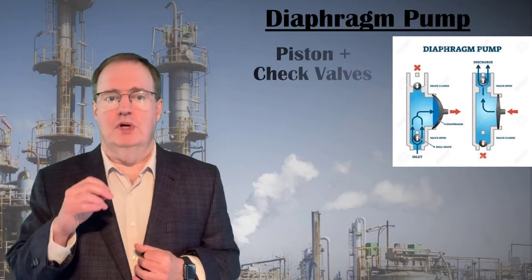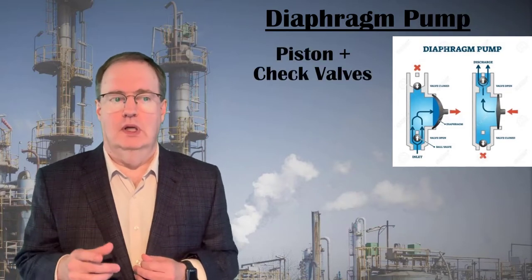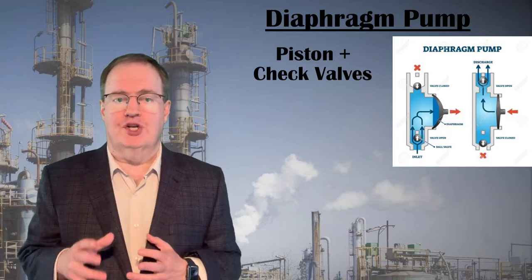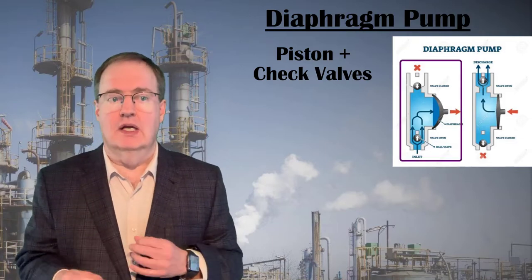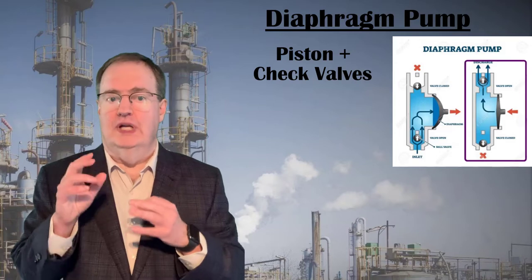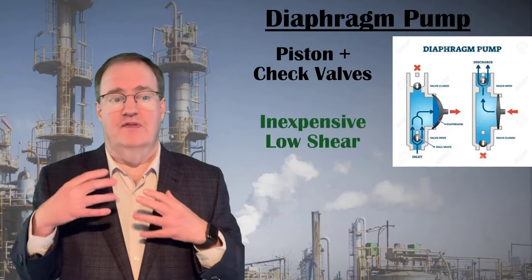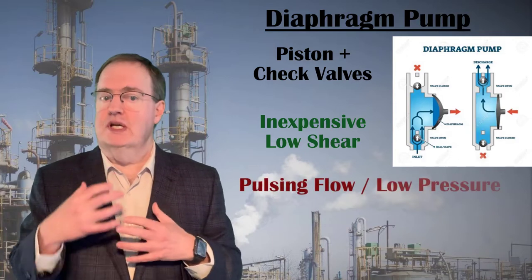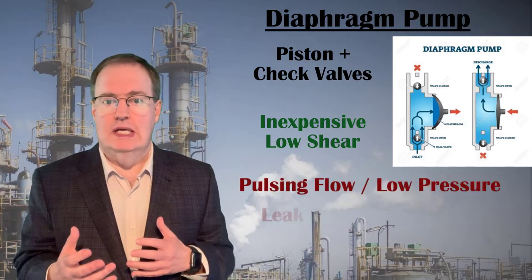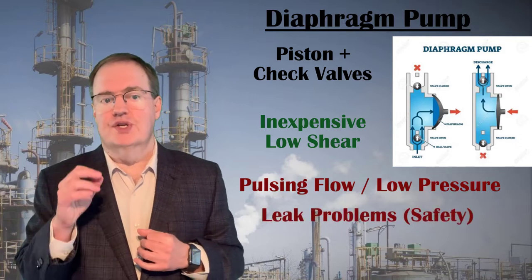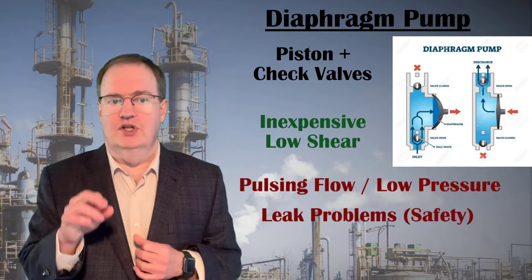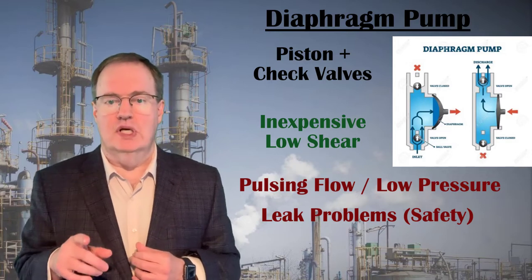Diaphragm pumps use a piston chamber combined with two check valves to force fluids forward. The check valves only allow flow in one direction, while the diaphragm and piston enlarges the chamber to pull fluid in the inlet, then shrinks the chamber to push fluid out the outlet. Diaphragm pumps are inexpensive and very low shear, but they deliver pulsing periodic flow at low pressures. The seals and check valves tend to leak, so there is a significant safety hazard with flammable or toxic fluids. The flow rate delivered depends on the frequency and amplitude of the piston movement. Many metering pumps are diaphragm pumps.